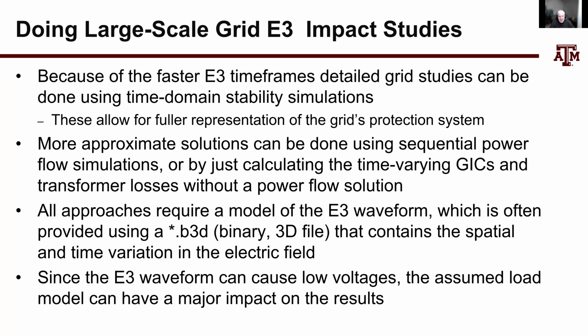Because of the time scale of the HEMP, we usually simulate these using a standard stability code that's also been enhanced to model GICs, so we calculate the GICs every time step in the stability simulation. Usually when running the stability code, we integrate at a quarter cycle or a half cycle, so every cycle we update the GIC values and update the reactive power loading.